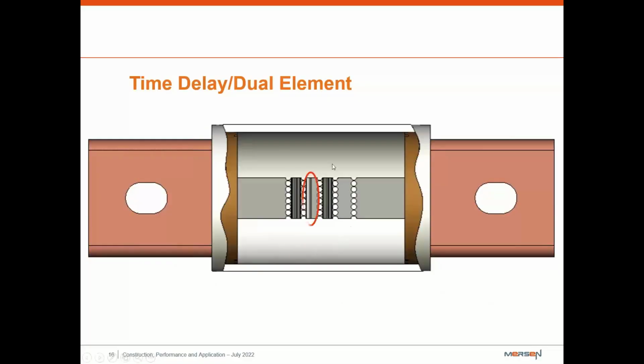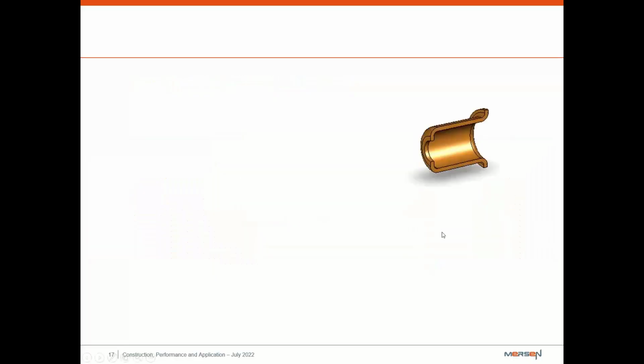So we have a piece of eutectic solder here in the middle, and with that, the principle applies that whenever current is flowing across this, it's not going to take 10 times the rating of the fuse to actually open up and burn away this material. It's just going to be enough to put energy into this piece of solder, right? So any guys that have ever soldered, you take the iron, you put it to the solder. As the heat increases, you'll change the state from a solid to a liquid. Once it turns into a liquid, it'll go away. The arc will continue to flow over the gap. It'll come in contact with that filler, the sand, and insulate the circuit.